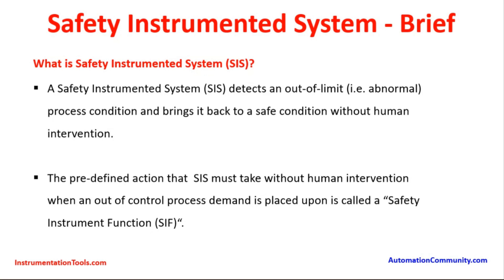What is a safety instrumented system? A safety instrumented system detects abnormal process conditions and brings the process back to a safe condition without human intervention. In process plants, normally a DCS — distributed control system — is working and doing the plant automatic operations. Whenever any hazardous conditions arise that the DCS control system cannot contain, the SIS system comes into action. The predefined action that SIS must take without human intervention when an out-of-control process demand is placed upon it is called a safety instrumented function.